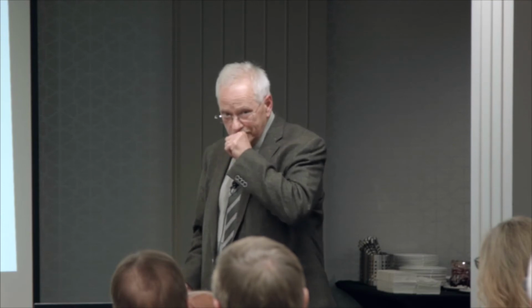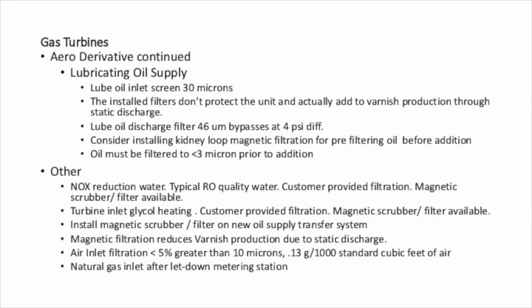So I have to add, he tells me what the filtration requirements are for the inlet to the turbine, and he tells me that any oil that goes into the turbine must be filtered to 3 microns. So that tells me right there, I have to pre-filter any oil I add to that turbine, because it sure isn't coming from the manufacturer at 3 microns. Lubricating oil supply: the lubricating inlet screen has to be 30 microns. That's what they provide you on the machine. The lube oil discharge filter is 46 microns, and it bypasses at 4 psi. Oil must be filtered to 3 microns prior to addition. That's what our turbine manufacturer demands.